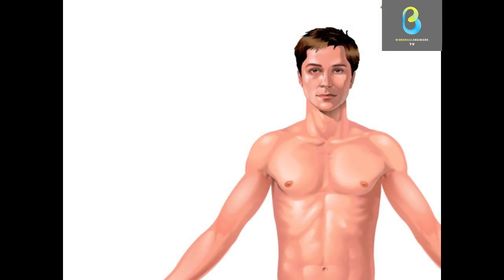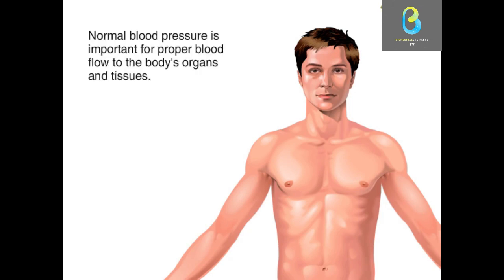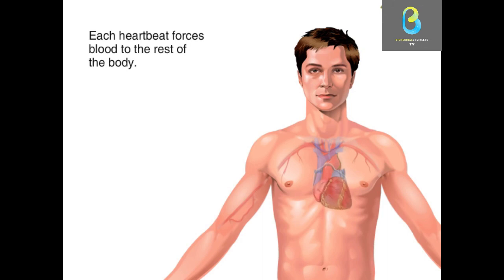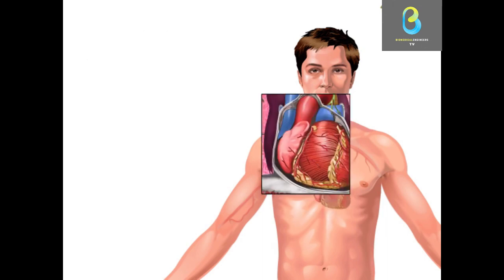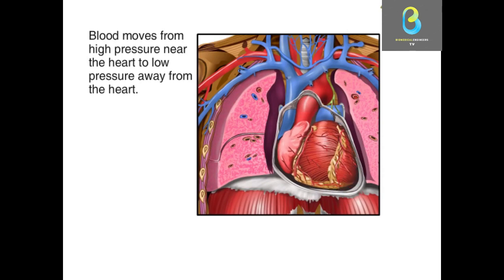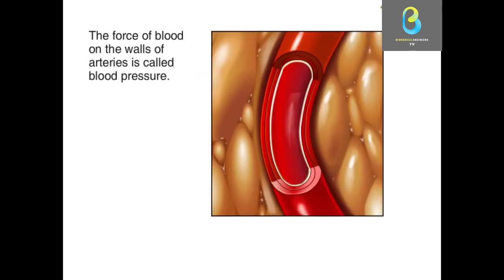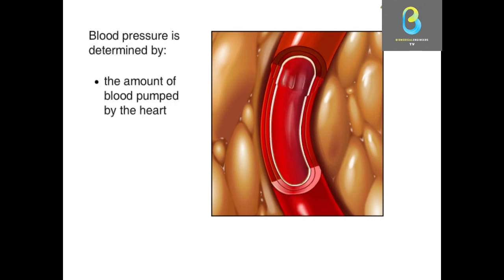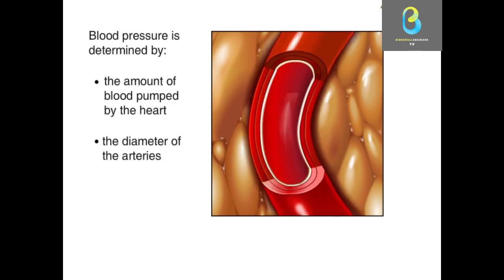Let's know about NIBP. Most of the patient monitoring systems are based on the oscillometric measuring principle. A number of automated blood pressure measuring instruments have been designed which make use of the Riva-Rocci method. This technique was introduced by Riva-Rocci for the determination of systolic and diastolic pressures. Initially, the pressure in the cuff is raised to a level well above the systolic pressure so that blood flow is completely terminated.